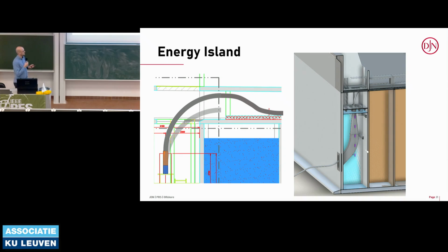It's actually a tricky thing, but as you know, we want the electrical system to be double-earthed on each side. But if you put your joint over here, that means you need earthing points. Concrete is a little bit conductive, but not enough, the area requires 0.1 ohm, so we need a cable for that. A cable needs to be installed into this top slab layer, where we install the earth points, such that we can install our joint at this location.